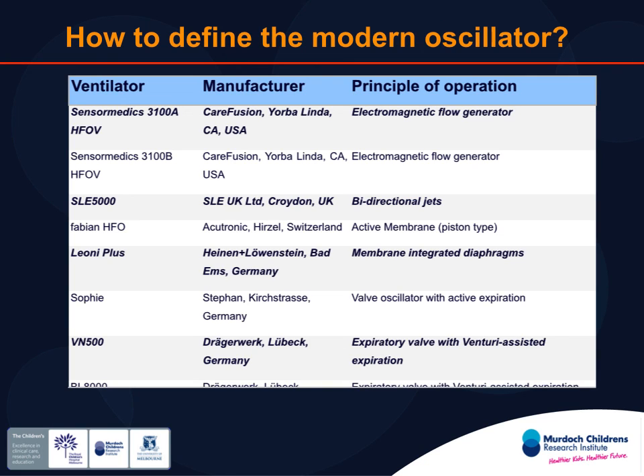The other thing we were interested in is this whole definition of the oscillator, the flow interrupter, and, as its own entity, the jet. Can we use that definition in the modern era? We put it to you that we can't, because none of these devices have the words flow interrupting or oscillator in terms of how they work. They all do things like bidirectional jets and membrane integrated diaphragms. I don't know what that even is. Valve oscillation, expiratory valve, venturi assist. It's all very complicated and not really classifiable anymore.